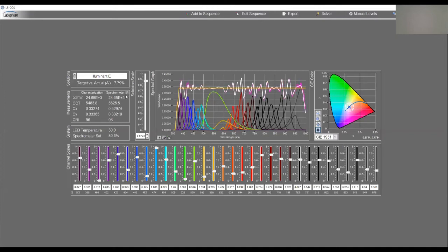And if I turn on the spectrometer, this is an embedded spectrometer inside the source, which is measuring the spectral radiance through the exit port. Now, this is giving you your metrics of how well the optimization is holding up. So it's important that the spectroradiometer always be calibrated. So how do we do that?